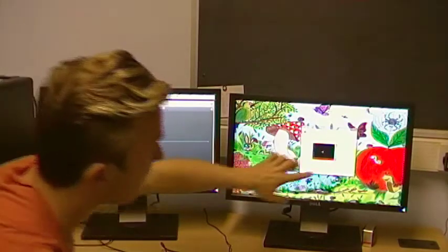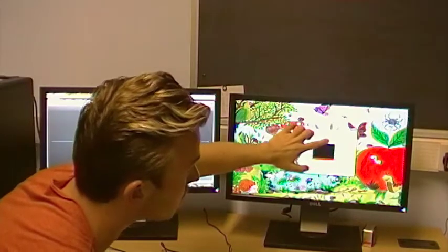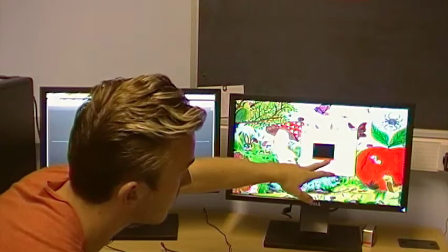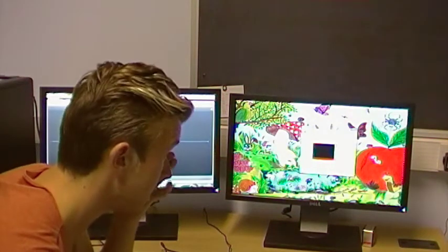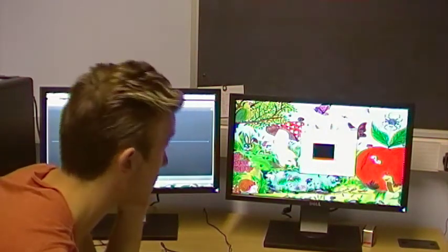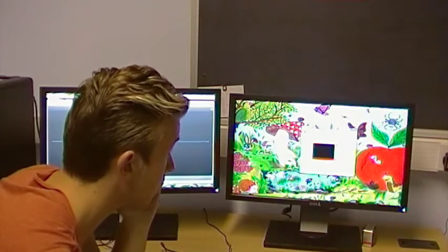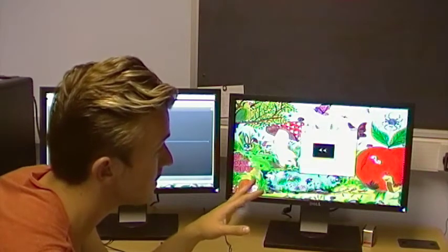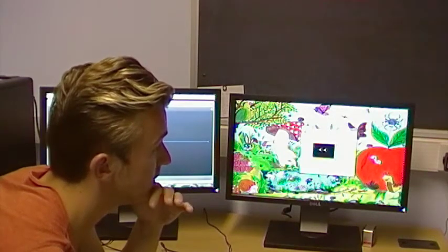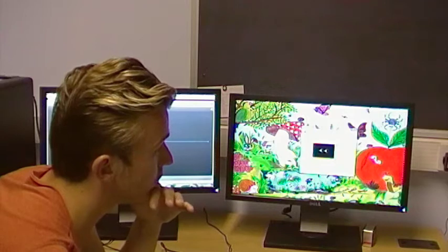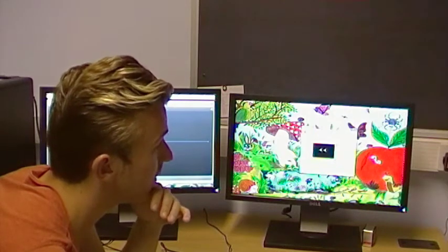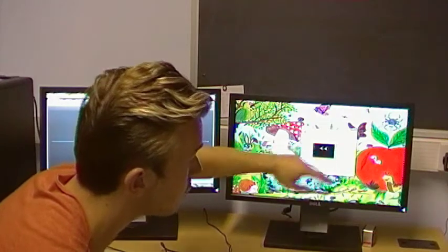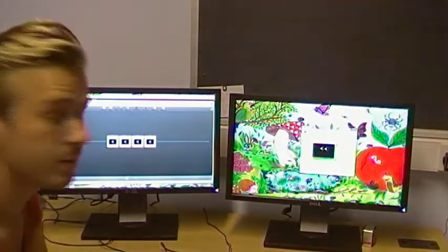This bar at the side here shows us the distance that the participant is away from the screen. It tells us the number in centimetres specifically, so at the moment it's having trouble picking up our participant's eyes. It's going back and forth, but here it's picked up perfectly. We can see that it's calculating the distance that the participant is away from the screen, going closer and closer, 52 centimetres and away. And what we need is for that white arrow to be in the middle of that green bar. That's best practice.